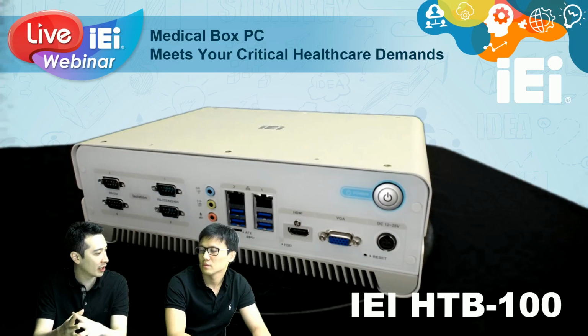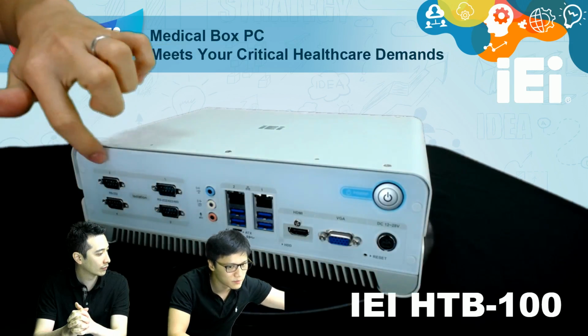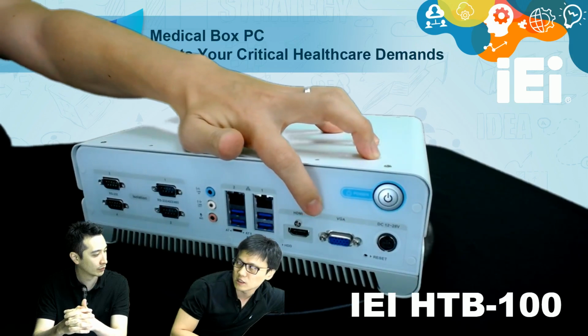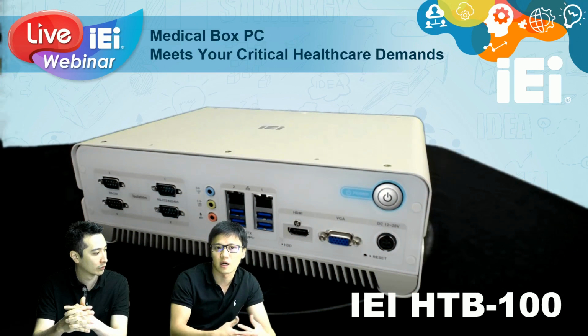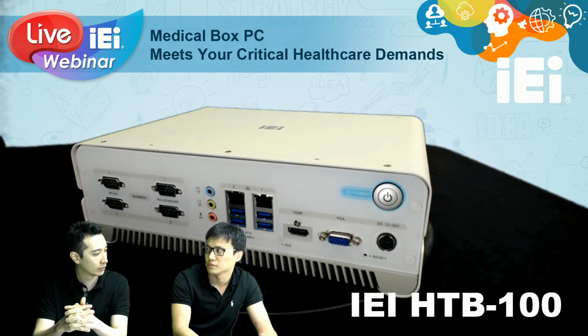Okay, what about the functionalities? From the functionality part, we have 4 COM ports here. We follow a medical grade design which supports 4 kV isolation. And we have 2 independent displays. One is VGA, the other one is lockable HDMI. Especially for HDMI, this port supports HDMI 2.0. And like I mentioned before, the doctor usually uses this kind of display to show the high-resolution image.